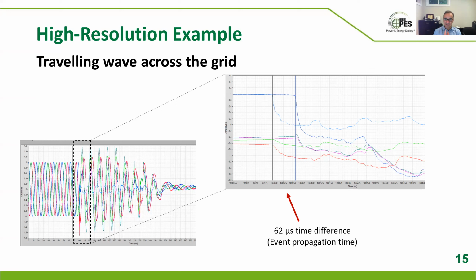But if I sample every microsecond, I have the ability to say when the wave arrived within a microsecond resolution. Let's say, in this case, it takes 80 microseconds for the wave to travel the line. The line length is 80 times 300, which is 24 kilometers. This is a 24 kilometer line, and it takes a traveling wave 80 microseconds to travel from one end to the other end.